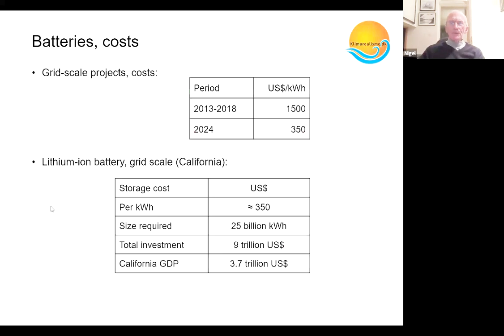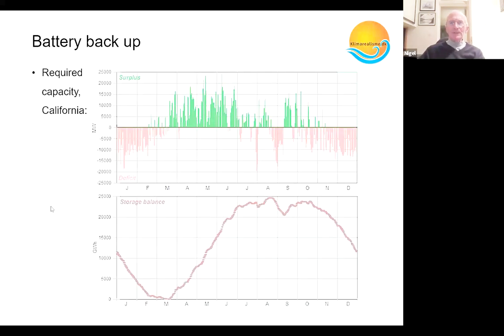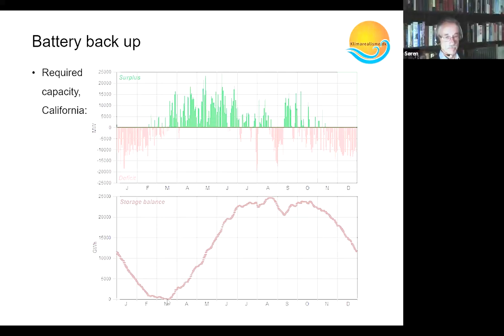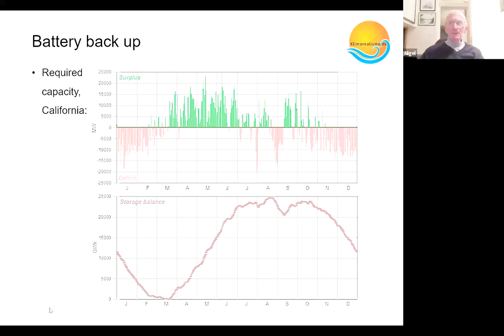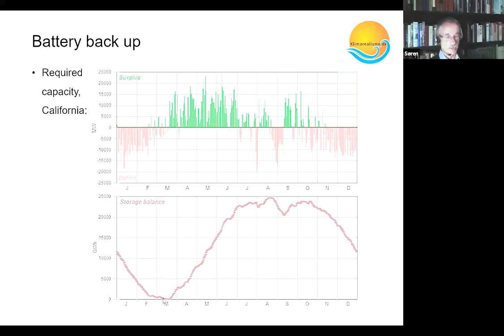Soren, is that where you're draining the battery down to zero, or down to some sort of 50% rate? This is down to zero. So you destroy the battery then? Yes, and that of course is the next problem—a battery should preferably be operated between 20 and 80% load. If you take that into account, you can more or less double the size. But we don't do that here because this is just a calculating example, and when we get the final figure, we can always add whatever we want. It doesn't look better when we do that.